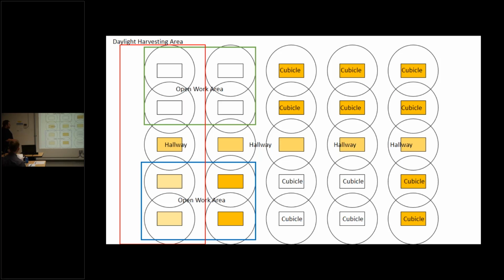So it knows this area is occupied and should be full on. But because it's reading illumination level from, let's pretend there are windows here, these 2 lights will dim while these ones remain on. Or if we increase that area, these guys would also dim, and they can dim at different percentages — this one dimming to 20%, this one to 60%.